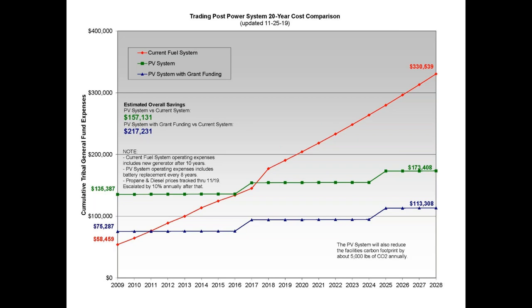Midway through, on the two green and blue graphs, there are two spikes in cost. The only real operating cost we've had, at the 8-year mark, was replacing the batteries. In the past, we went with lead acid batteries because that's all there really was — 6-volt lead acid batteries, shown on one of the earlier slides. They basically run two sets of eight that generate a 48-volt system.